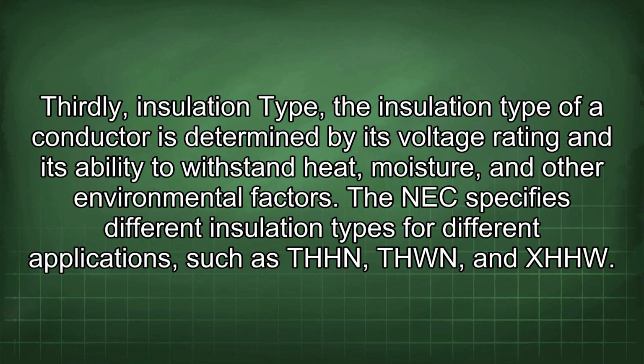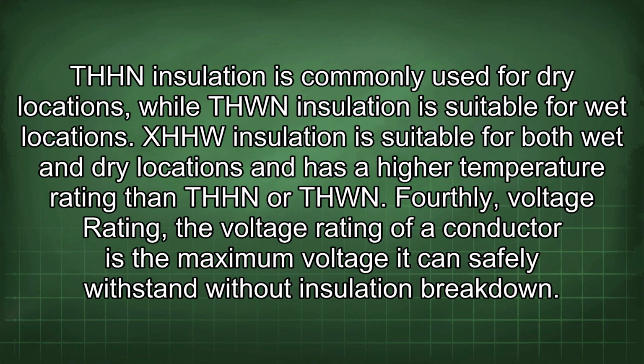Thirdly, insulation type. The insulation type of a conductor is determined by its voltage rating and its ability to withstand heat, moisture, and other environmental factors. The NEC specifies different insulation types for different applications, such as THHN, THWN, and XHHW. THHN insulation is commonly used for dry locations, while THWN insulation is suitable for wet locations. XHHW insulation is suitable for both wet and dry locations and has a higher temperature rating than THHN or THWN.